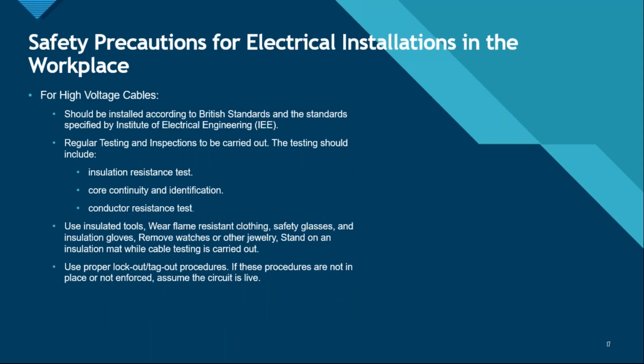Then the high voltage cables. High voltage cables should be installed according to British standards and the standards specified by the Institute of Electrical Engineering. Regular testing and inspections need to be carried out for the high voltage cables as well. They should have an IR test, an insulation resistance test. Usually we use Megger kits for the insulation resistance test, and that has to be done. Also core continuity and identification, and a conductor resistance test. Right, the resistance of the conductor present inside the high voltage cable also needs to be checked.